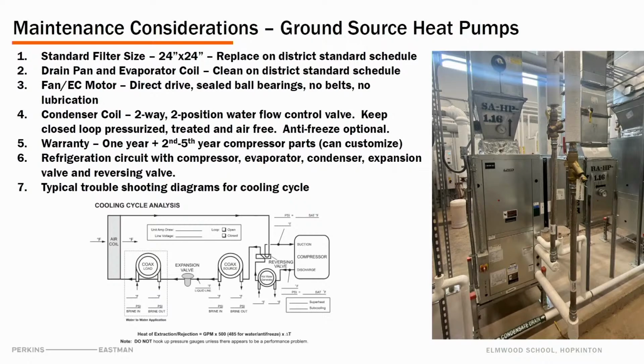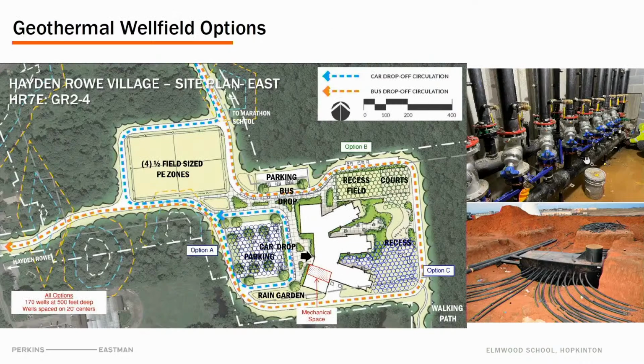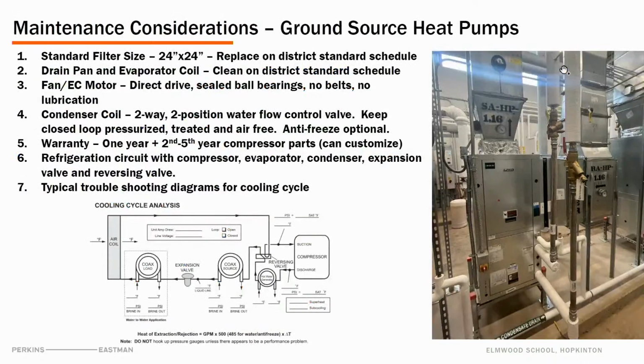Each heat pump has a fan in it that blows the air back and forth. The fan is behind this panel right here. It's connected to this duct. This duct is blowing air up, and it's sucking it back this way. So that fan sits in here and blows air that way. These are what we call direct drive fans. There are no belts on it that we have to worry about squeaking or breaking and repairing, which is helpful from a maintenance perspective. So there's no lubrication for it. Again, the motors can fail, but those motors can be replaced pretty easily. These are like 1/2 horsepower motors, so they're not very big, and they can be replaced pretty quickly.